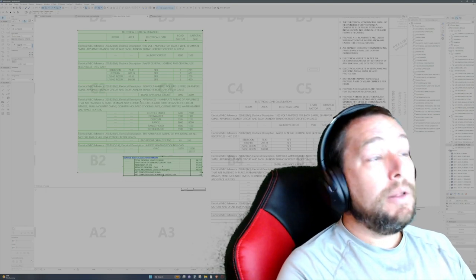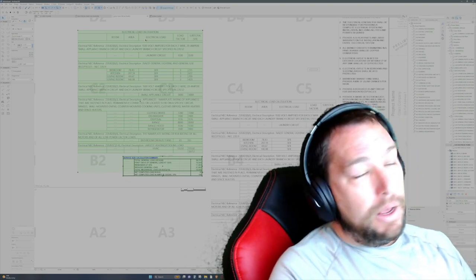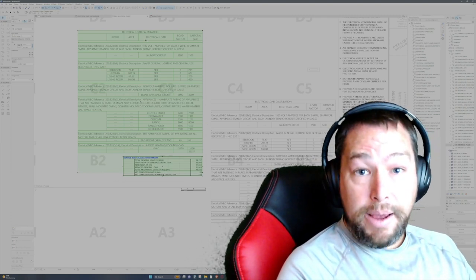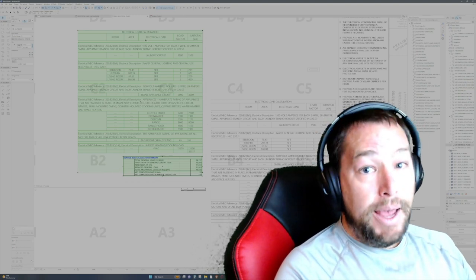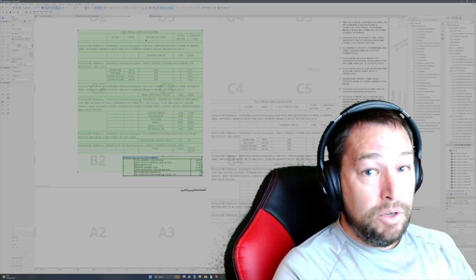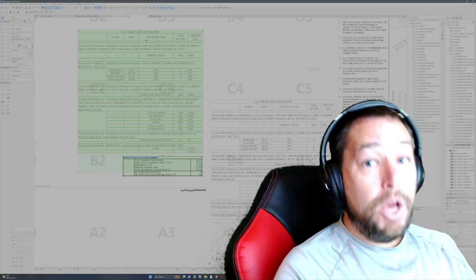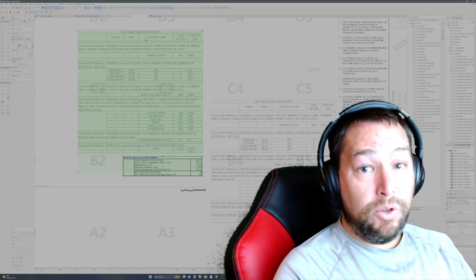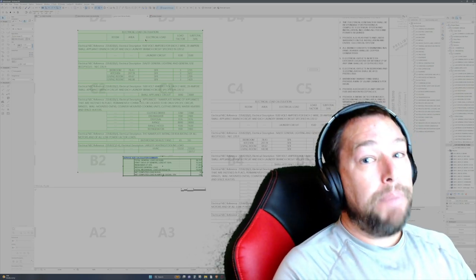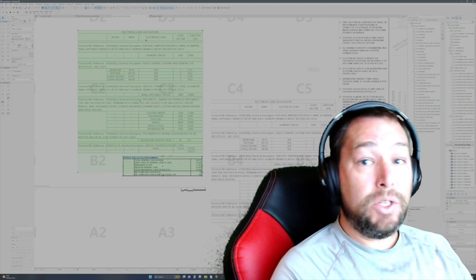It says 3 volt amps per square foot, so on a 1,000 square foot residence, you're looking at 3,000 volt amps that you need to provide. But in addition to the square footage calculation, you also need to provide for point loads from specific electrical loads, like your washer and dryer, and depending on how many you have, that may factor into how much you reduce that load.